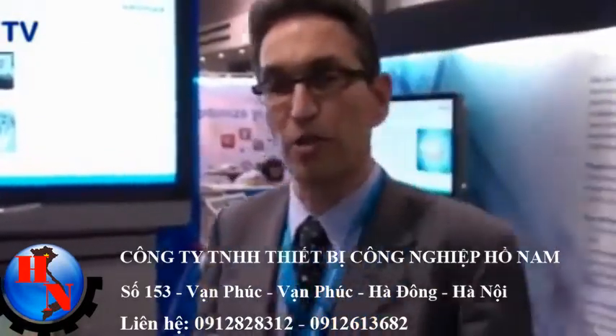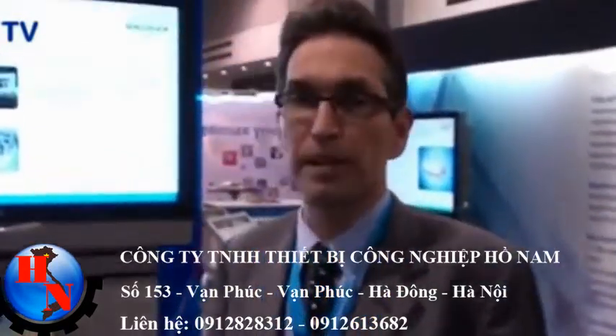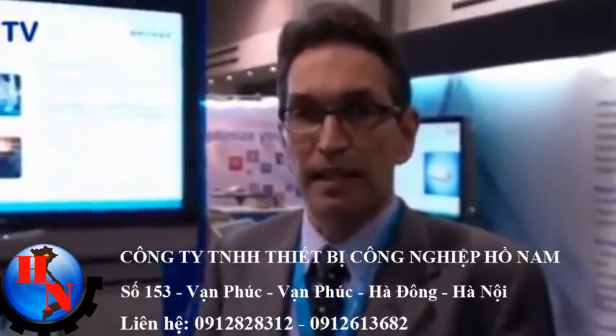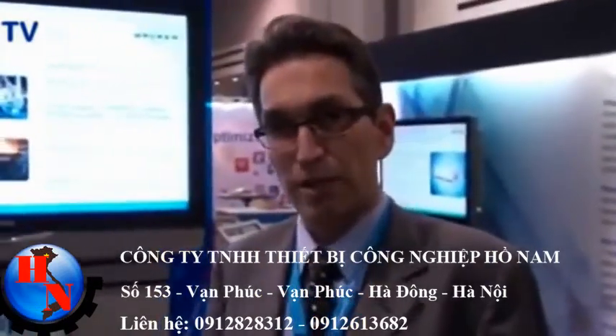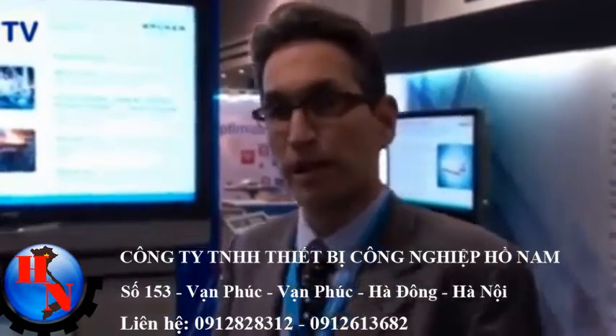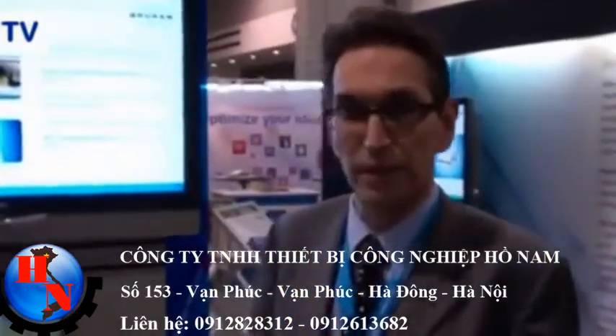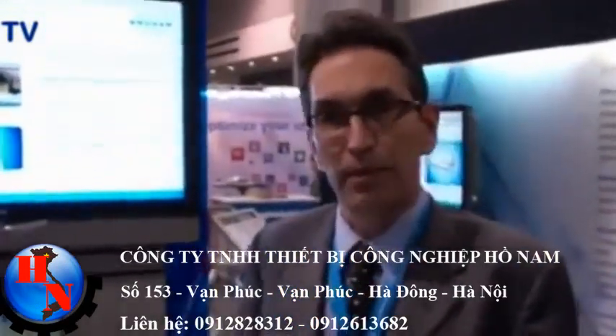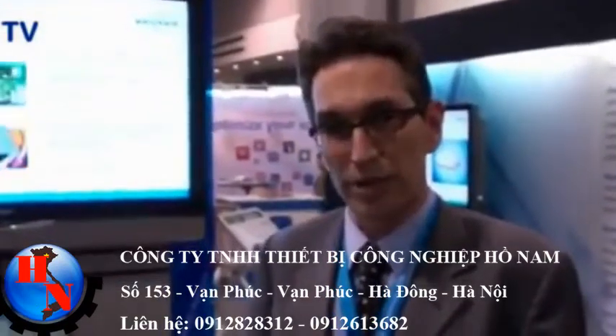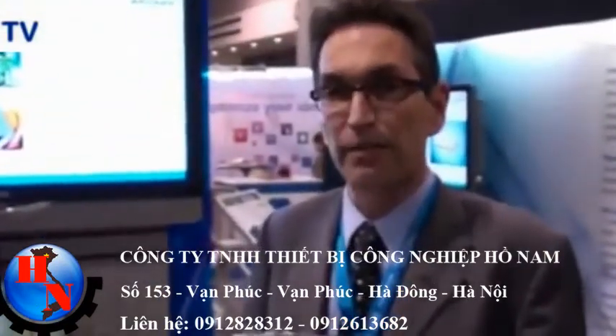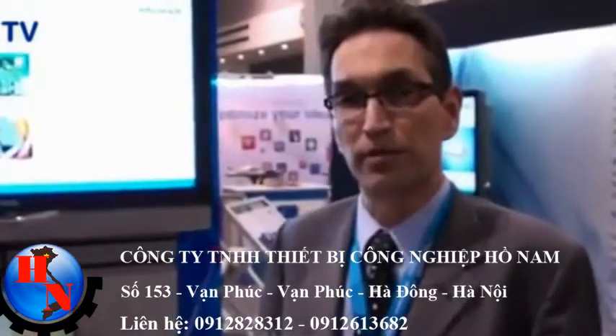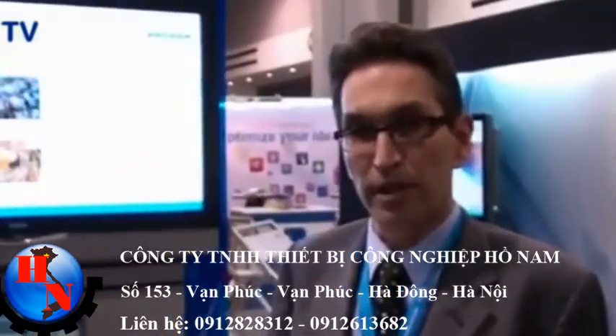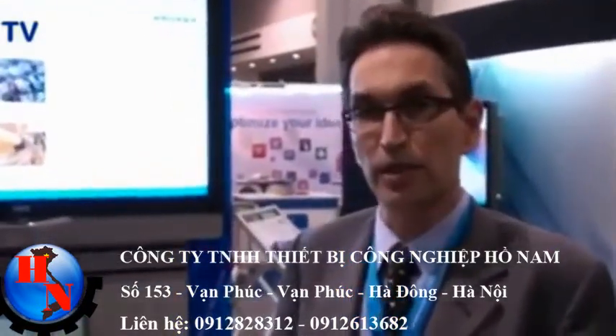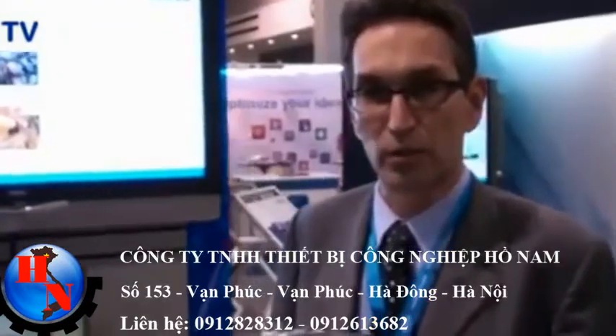The Tracer 4 Geo fills a definite opening, which means that instead of using a factory calibration, the unit is equipped with our S-Spectra EDX software, which allows the users to make their own calibrations and modify every factory calibration which we provide for them. All factory calibrations from our handheld S1 series are available on this unit as well.